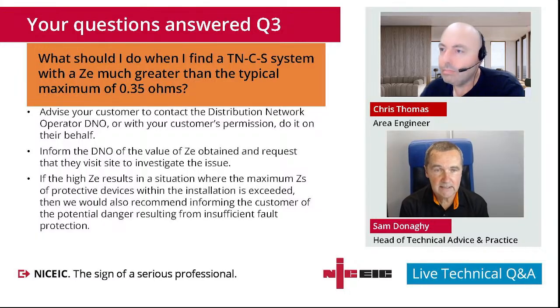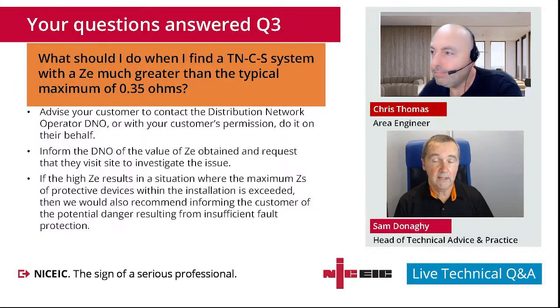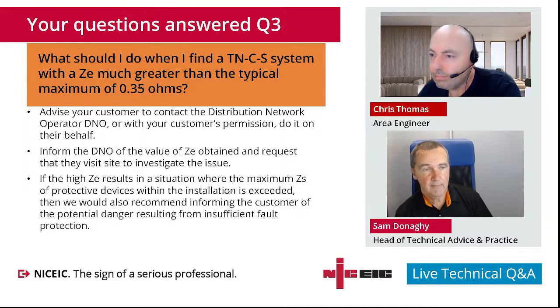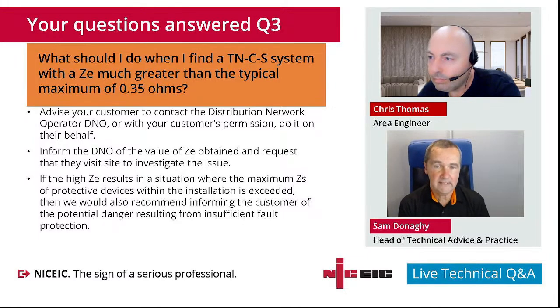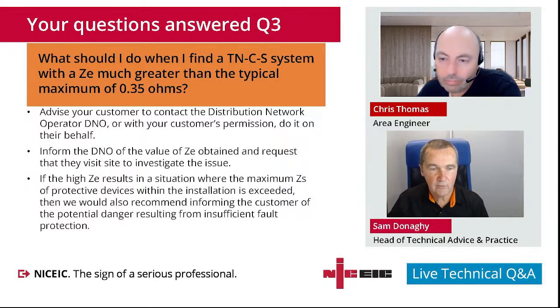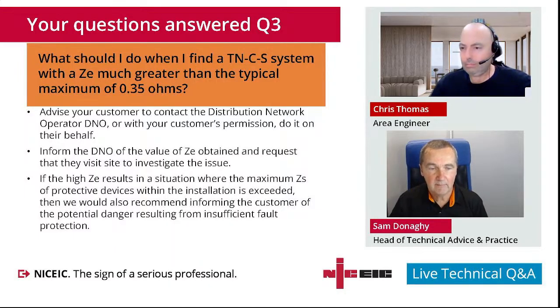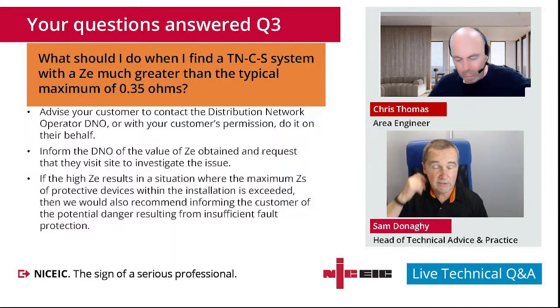It really is a case of them making sure that there's no evidence in what you measure to indicate that there's an issue with the network, i.e., has it drastically gone up in resistance since they last installed it? So that's why they may not be too concerned if they've known that it's been, as a typical example, measured at 0.5 regularly, then they won't have an issue with the fact that it's greater than 0.35 so long as it remains stable.